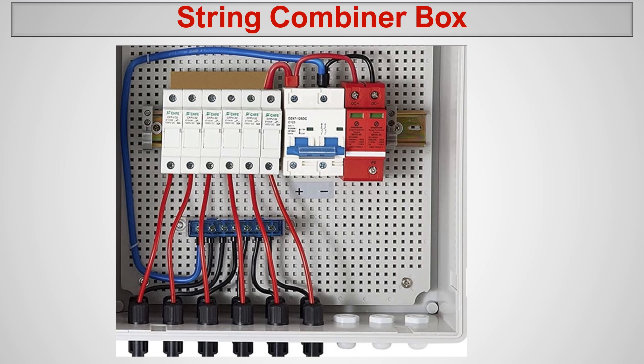Now let's look at how a string combiner box actually looks. By looking at these wires we can see we have six strings — one, two, three, four, five, six — coming into the connection. This means six sets of panels on the roof are wired in series. For example, five panels in series, another five panels in series, and so on — six sets of series-connected panels coming to the combiner box.